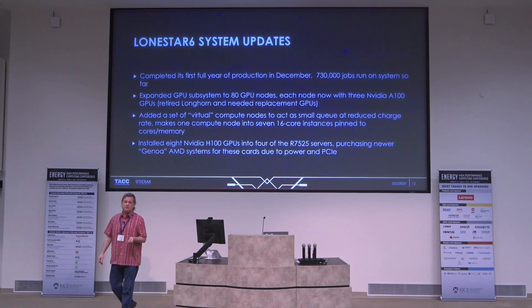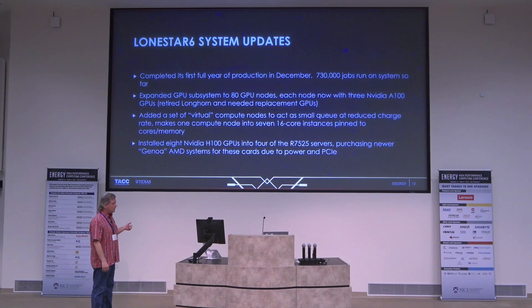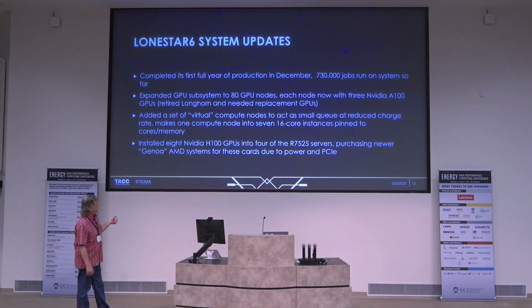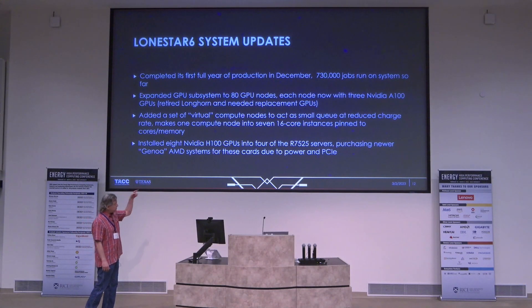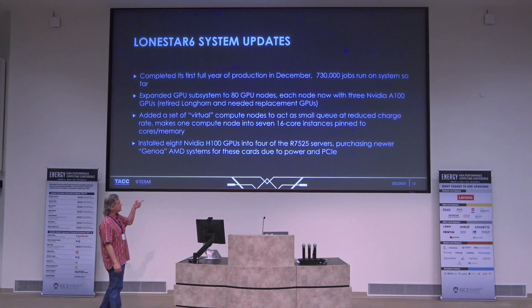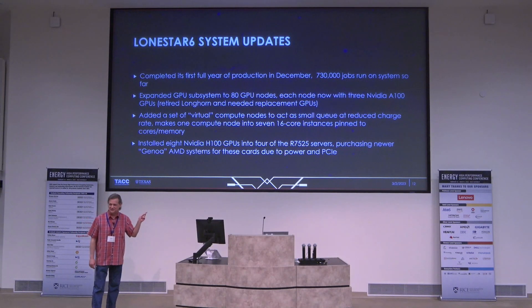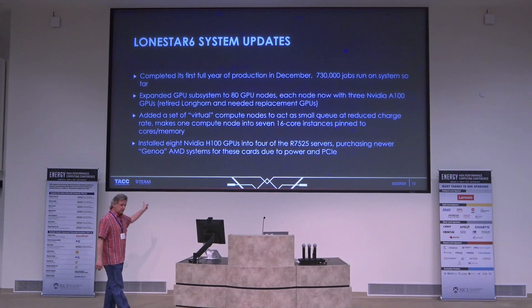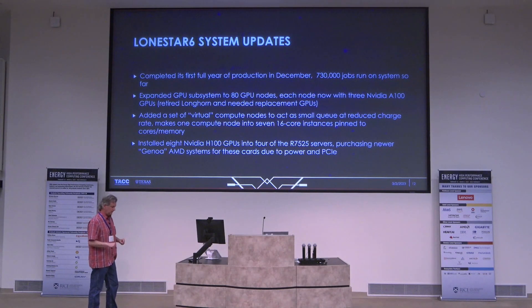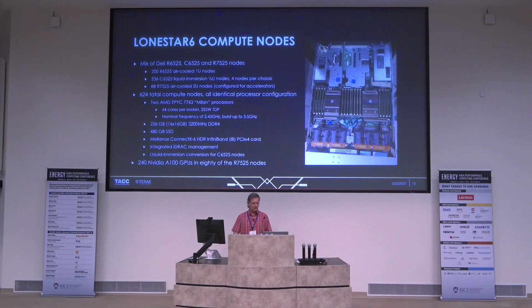We got eight brand new H100s and they are quite impressive. The downside is they didn't get a lot more memory bandwidth — about a 30% improvement compared to the A100s — but the core count and flops are almost double what the A100s provide. One challenge is these GPUs are PCIe gen 5 while our old servers are gen 4, and our servers weren't designed to deliver the power needed — they'll only run up to about 310 watts per card and the cards need 350 watts each. So we just purchased new Genoa servers with PCIe gen 5 and more power delivery so we can install the H100s and get full power out of them.